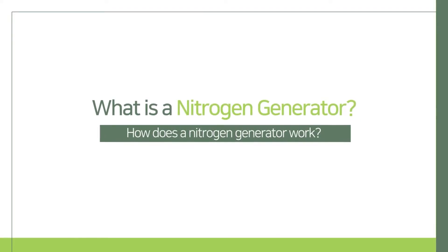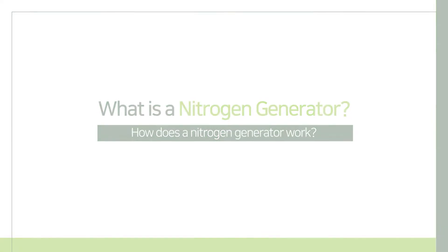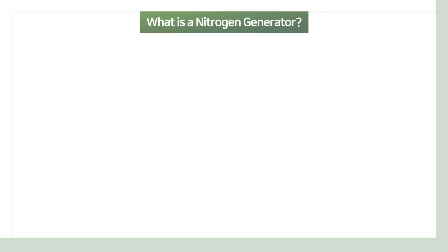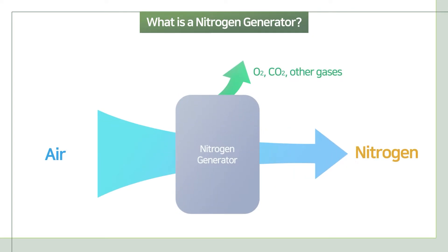Let's learn about what a nitrogen generator is and how it works. A nitrogen generator requires a compressed air supply to produce nitrogen gas. The compressed air is passed through the nitrogen generator to separate nitrogen out from the other elements like oxygen and carbon dioxide in the air.